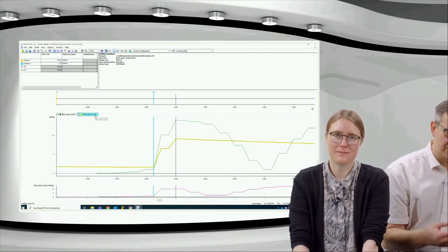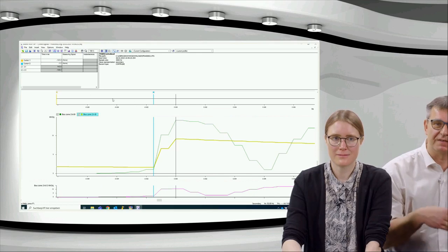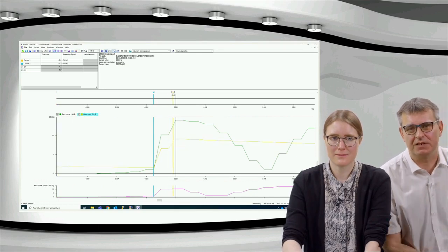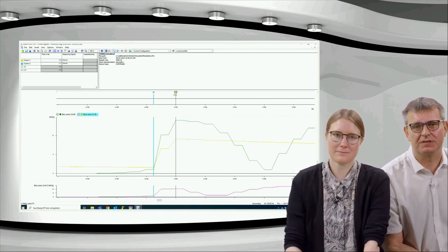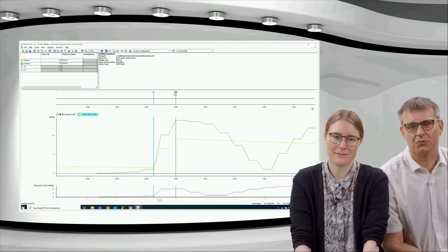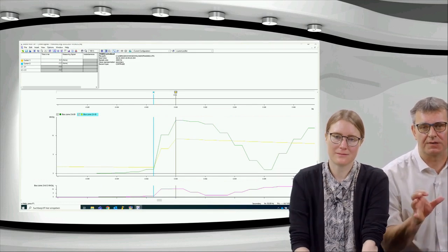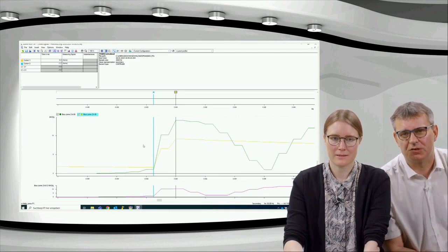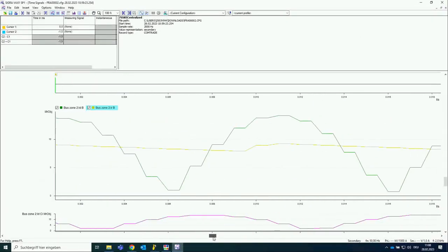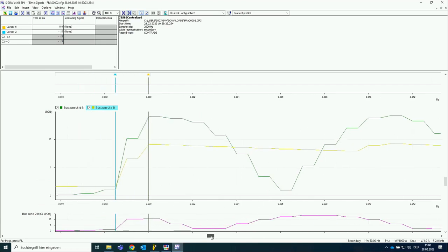as long as the calculated stabilization current is increasing. As soon as the calculated stabilization current is decreasing, it's not decreasing sinusoidally. It's decreasing a little bit in a linearized way. You see it here, this decreasing after the zero, after the black line. That's no sinusoidal decreasing, it's really this linearized, modified decreasing. Exactly. Though when it's increasing again, and here, once again, the calculated stabilizing current is higher than the modified, and then it's decreasing again.